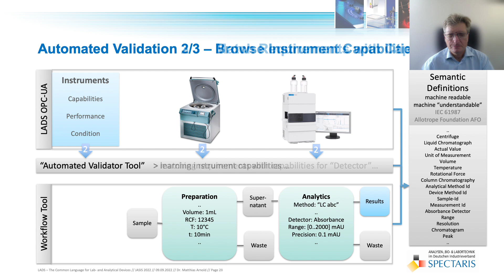They enable a precise, machine interpretable understanding of the meaning and role of the various information elements found in instruments and the process specification. In the image shown on the slide, the validator just takes a closer look at the detector of the HPLC. The detector type of the instrument, an absorbance detector, meets the specification. Its measurement range meets the specification. The same applies to its precision, and so on.